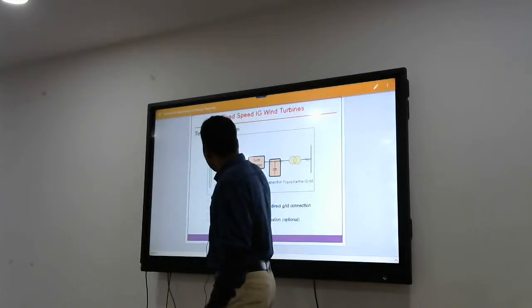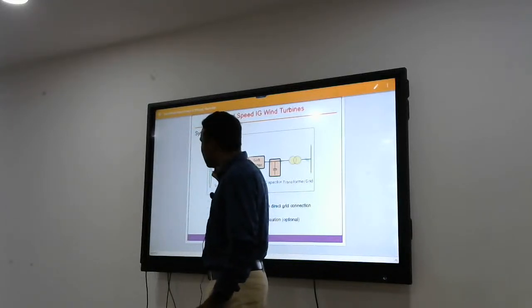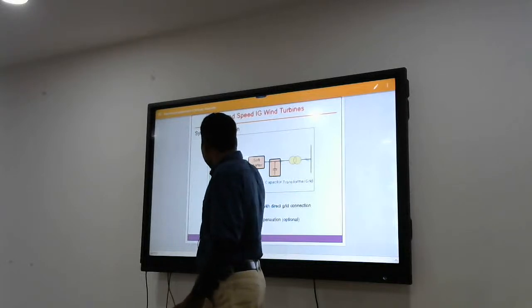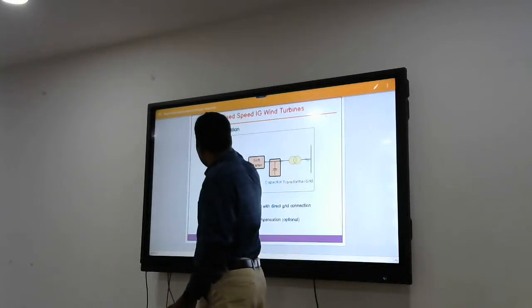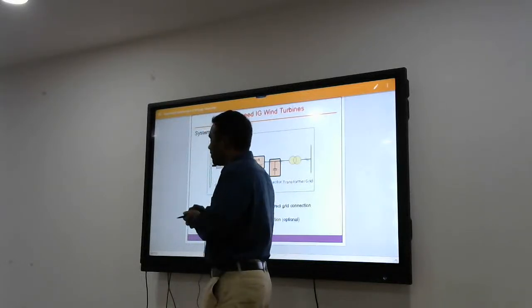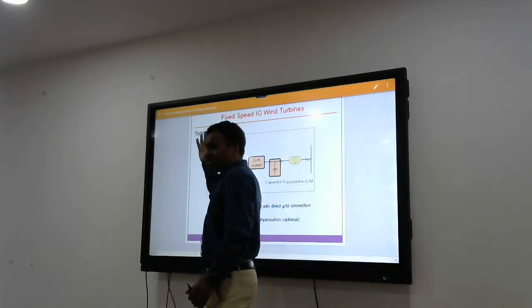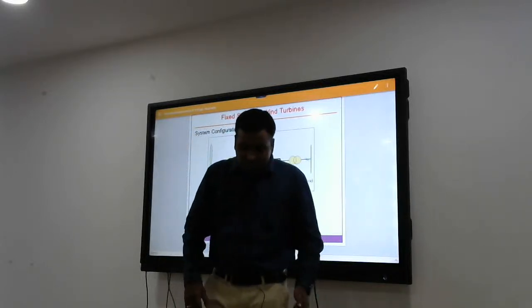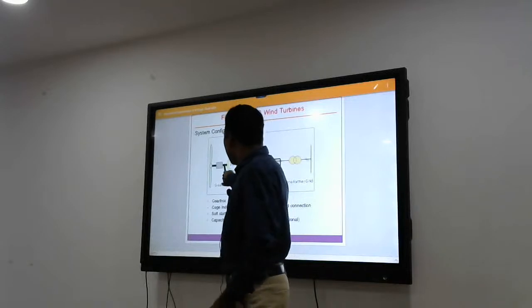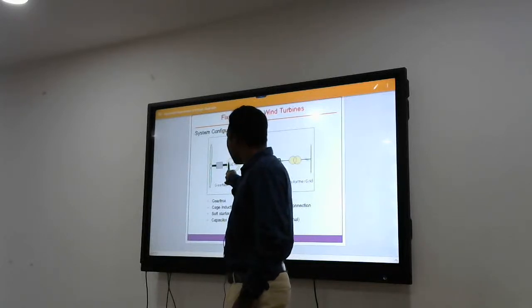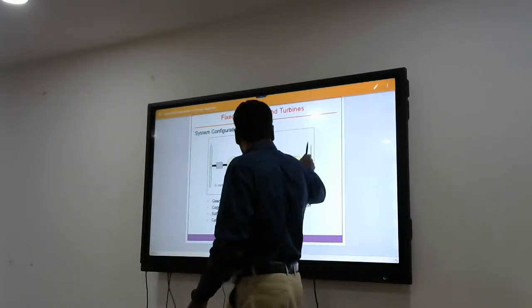Now, how can you change the speed? With the help of this gearbox, as I mentioned before, by changing the gearbox, and also by changing the pitch angle here, you can change the rotor speed. By changing this, you make your speed greater than synchronous speed, and this will enter into generation. This will be fed to the grid.